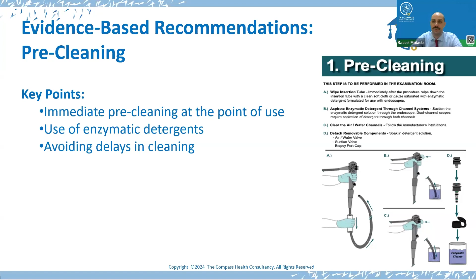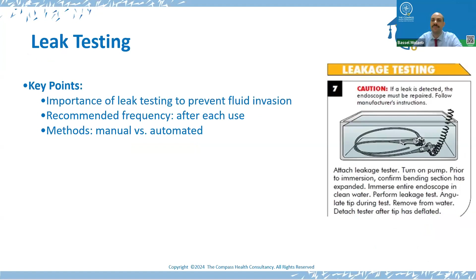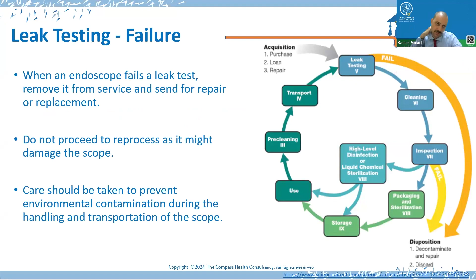Leak testing should be performed after each use and before use of a new, repaired, or loaned endoscope. It must be done in accordance with the endoscope and leak testing equipment IFUs, whether it is done by the automated method or the manual method. So what happens if you have a leak testing failure? You need to remove it from service and send it for repair or replacement. You should not proceed to reprocess it, as it might damage the scope. And you should be careful to prevent environmental contamination during the handling and transportation of the scope after failing the leak test.